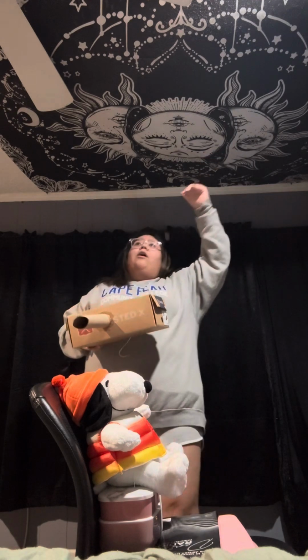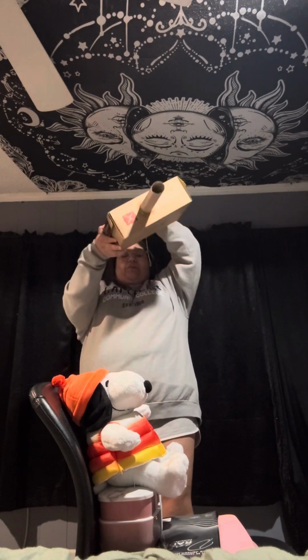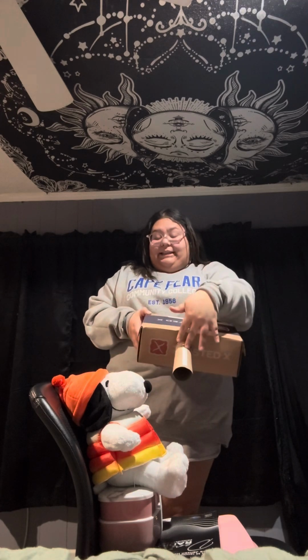So over here is our tube head, and this is what we use to actually take the dental x-rays. Let's say this is our patient over here, Mr. Snoopy. We would put a sensor into his mouth. We would locate the extension arm, rotate it to wherever it needed to be, and then adjust our PID, which is our positioning indicating device, to wherever it would need to be positioned. If we're doing molars, it's more towards the back of the mouth, premolars a little bit more forward. Then we would go outside to the control panel, select the settings, and take our x-ray.